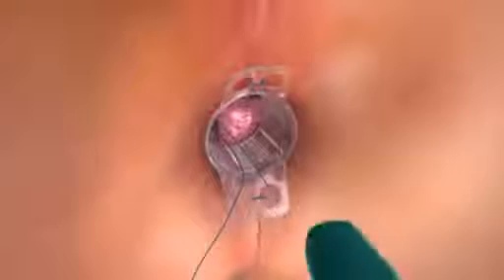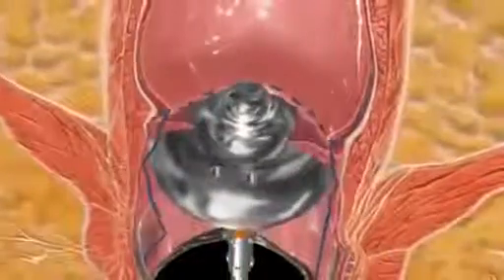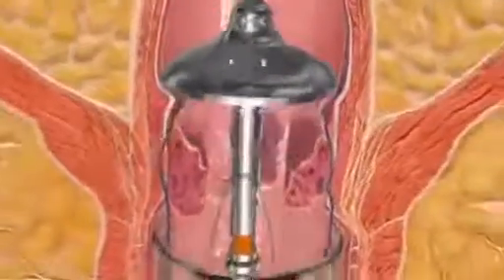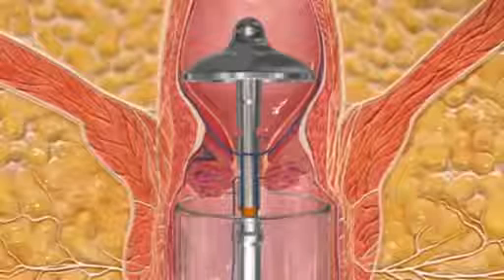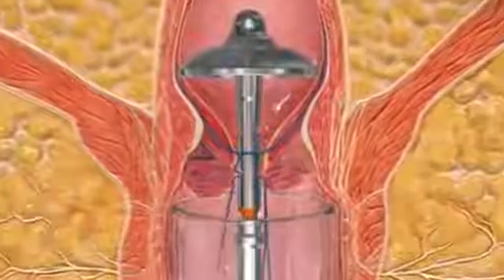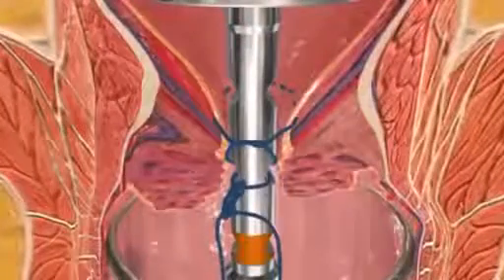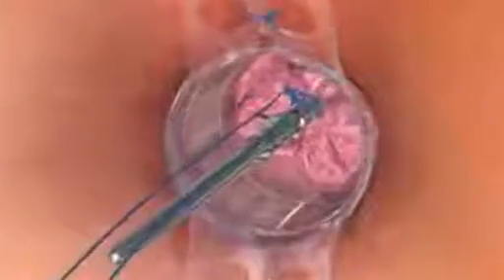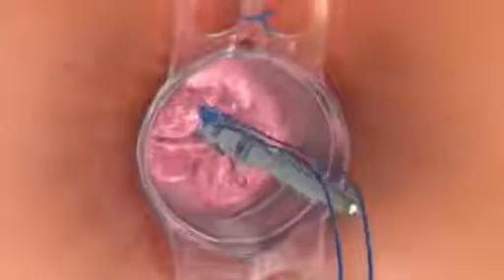Digitally or visually assess the amount of tissue to be resected and select an appropriate anchor hole on the center rod. Insert the detachable anvil into the rectum so that the anvil is positioned proximal to the purse-string suture. Cinch the purse-string suture around the center rod and pass one end of the suture through the appropriate anchor hole in the center rod. Pass the other end of the suture through the same hole but in the opposite direction. Secure the tissue to the center rod with appropriate purse-string tension and knotting. Visually or digitally inspect the tissues captured by the purse-string to ensure that only desired tissues have been incorporated and that there are no gaps in the purse-string.